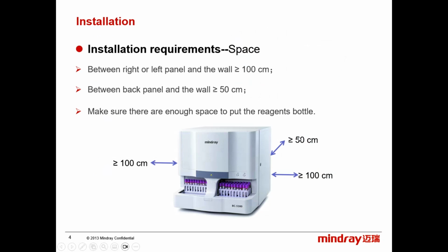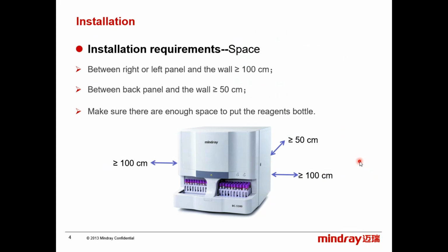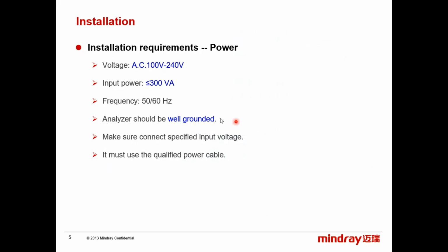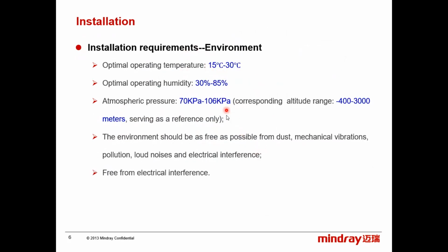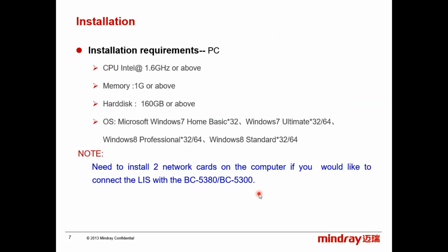Okay, so for the space requirement, for the power requirement, of course, very, very important to ensure that we have a good ground. Otherwise, you will have so many interference with the impedance channel. This is for the environment requirements like temperature, humidity, and so on. For the computer, normally now you can get much better than these specifications. You can get with Windows 10 directly now. It is compatible with Windows 10.